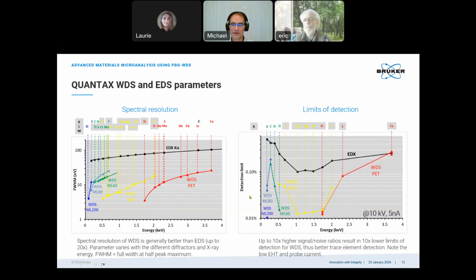Another parameter is detection limit. So this determines how well we can determine trace elements in the sample, and we compare here once again EDS with a black line, and the colored lines show WDS. These are measured parameters, so measured values, measured at fairly low primary energy, only 10 kV, 5 nanoampere. So these are the results from these low energies. And with higher energy, we would clearly get even better values.